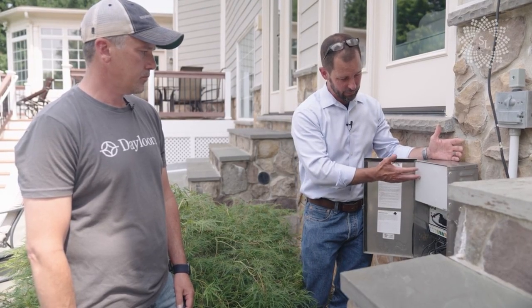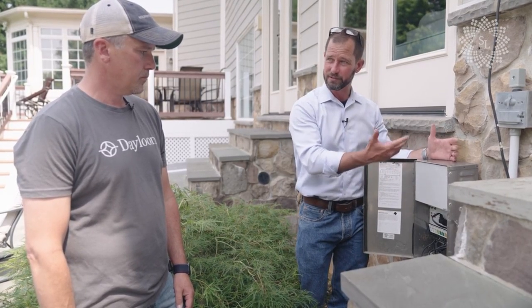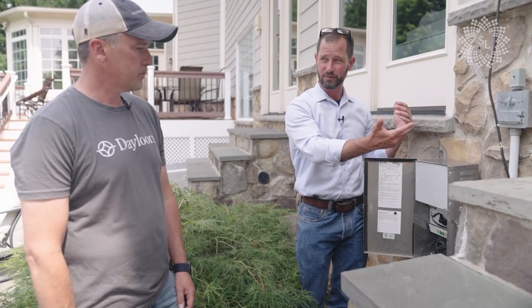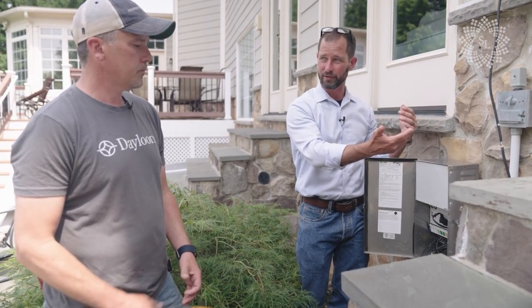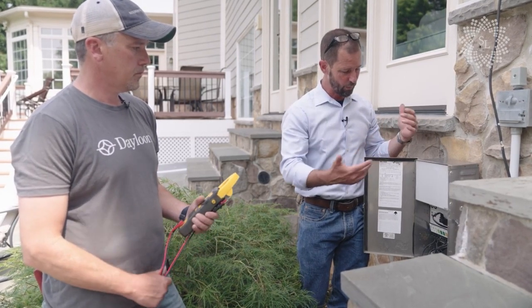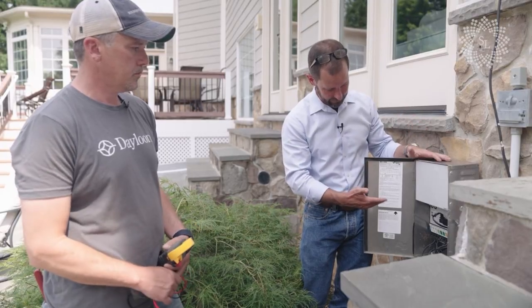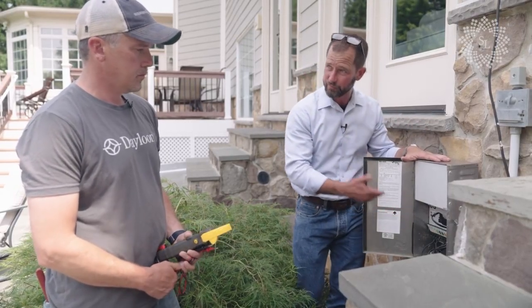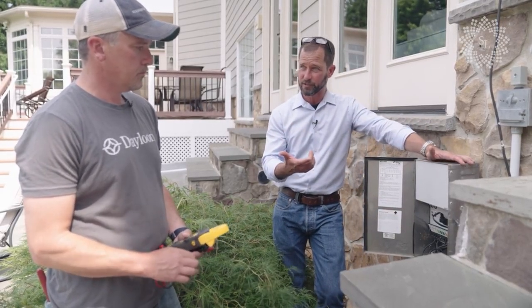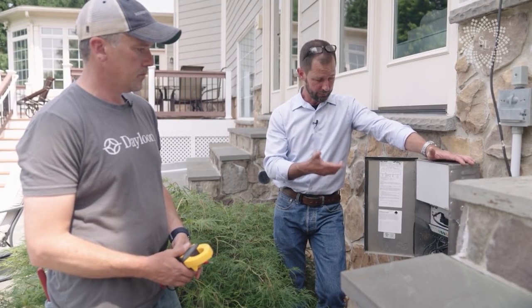So this is a transformer we can use. Even though it's rated 900 watts, with an LED system we're probably at about 130 to 140 watts total, so we have more than enough capacity. Next we're going to look at the voltage coming out, the overall amperage, and the amperage on the low voltage side.